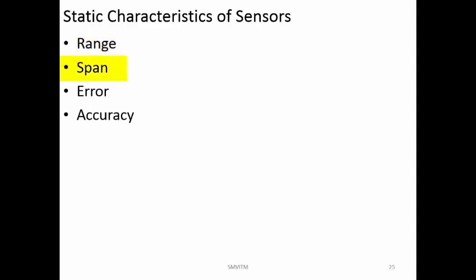Now what is span? Span is the difference between the maximum value that a sensor can detect and the minimum value the sensor can detect. For example, if a sensor has a range of say 0 to 100, then the span is 100. If the sensor has a range of 100 to 200, then also the span is 100. So a sensor can have different ranges, but the same span. So that is range and span.